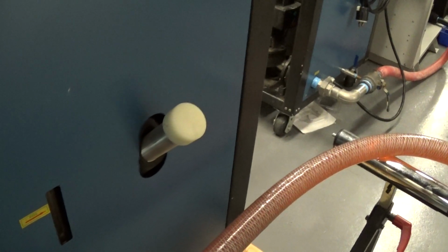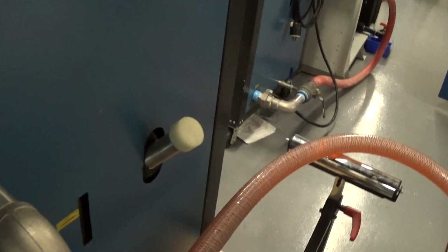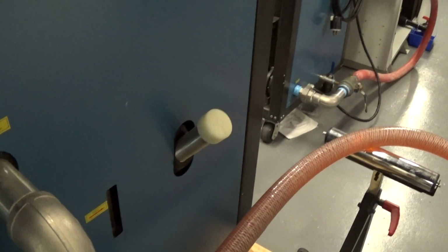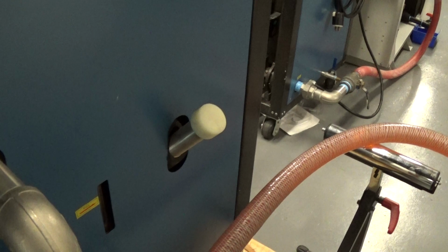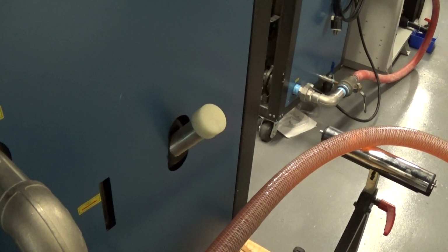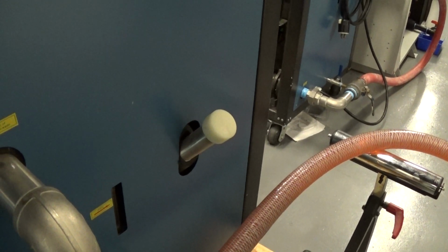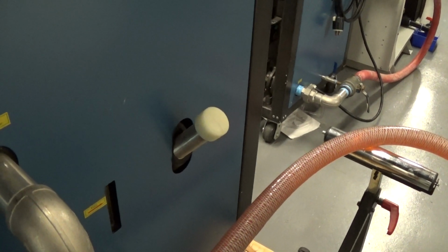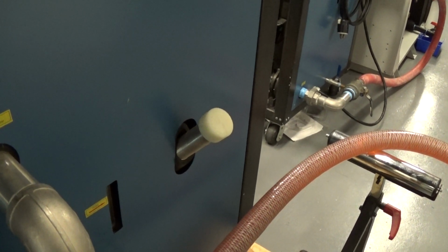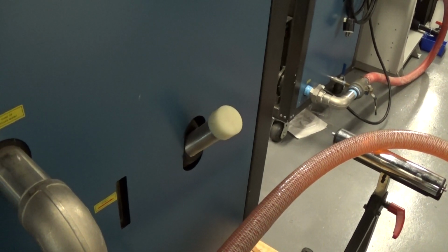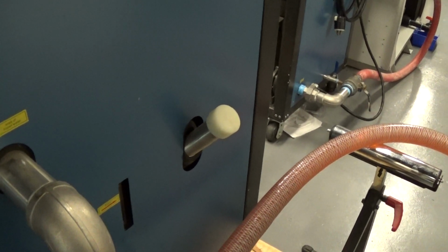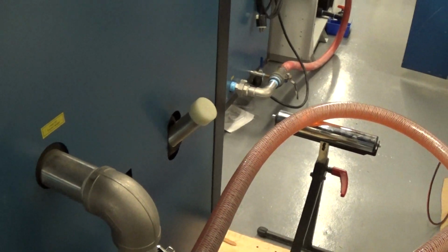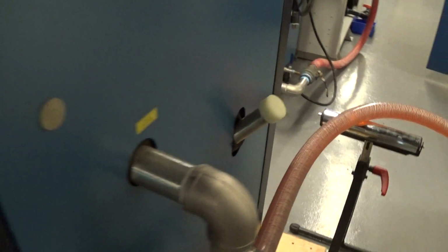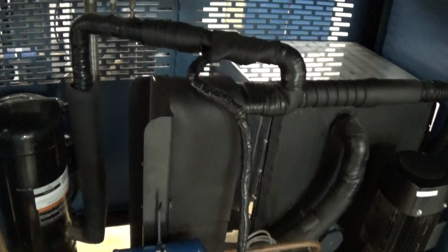This here is your fill port. That's where you should fill it with water or glycol. If you're going to run straight water, we always recommend running some glycol. If you're going to run straight water, I would not run the unit below 8 or 9C. The controller allows us to run down to 3C, which is about 38 or 39 Fahrenheit, give or take. But you really shouldn't run below about 48 Fahrenheit with straight water, because you could get freeze-up conditions inside this brazed plate evaporator here.